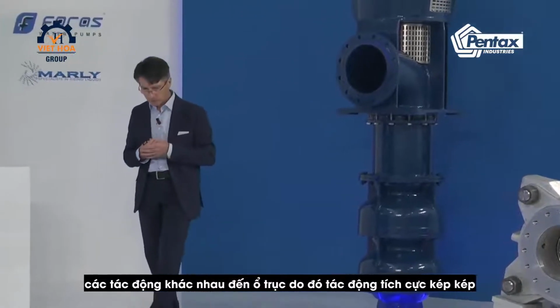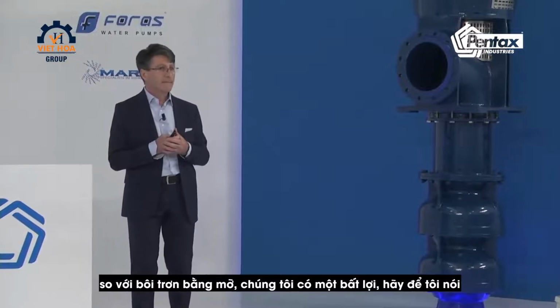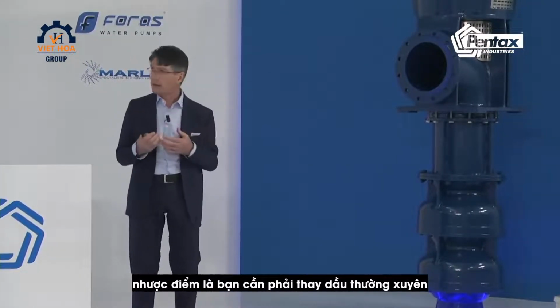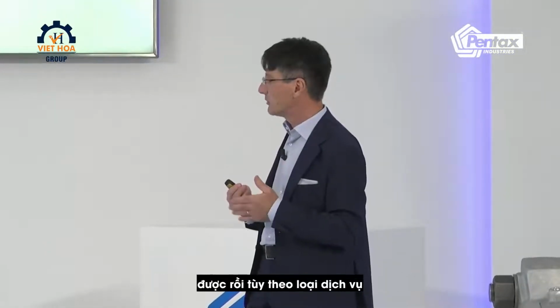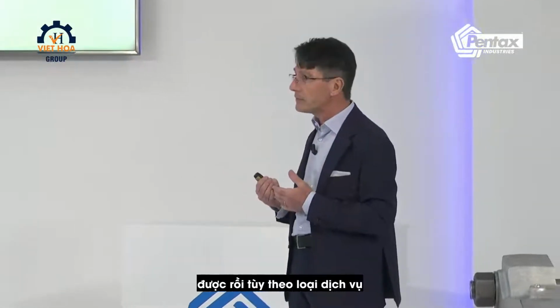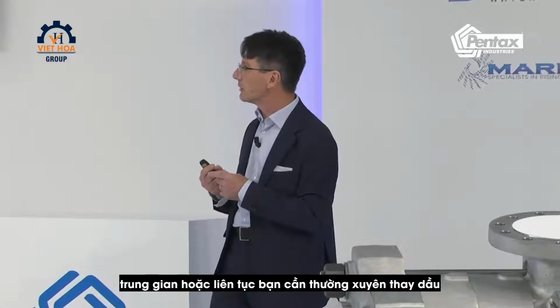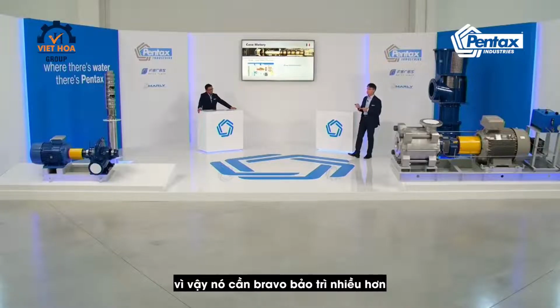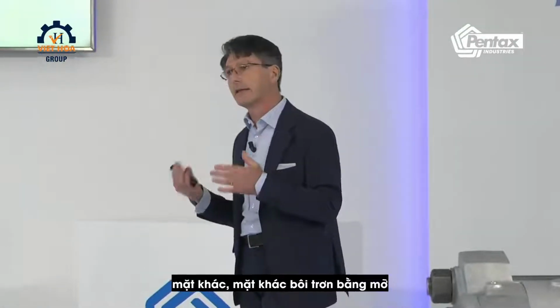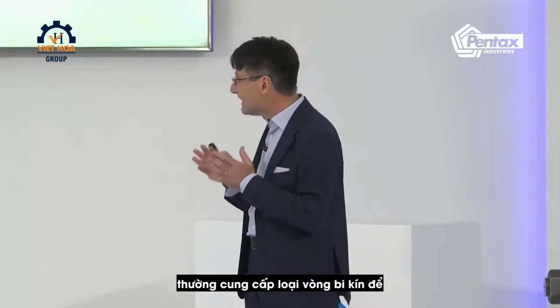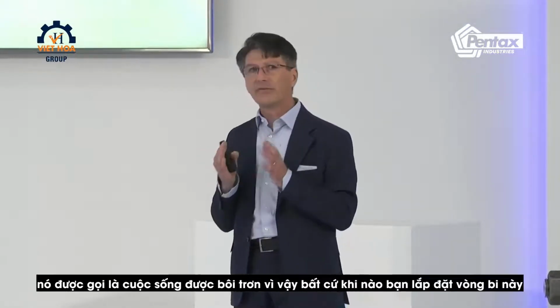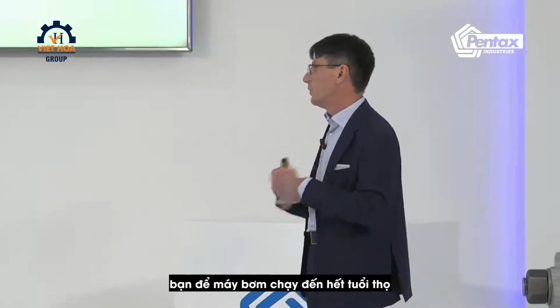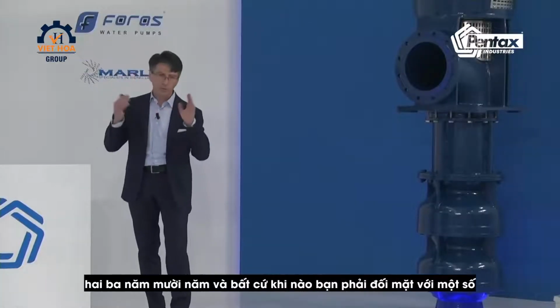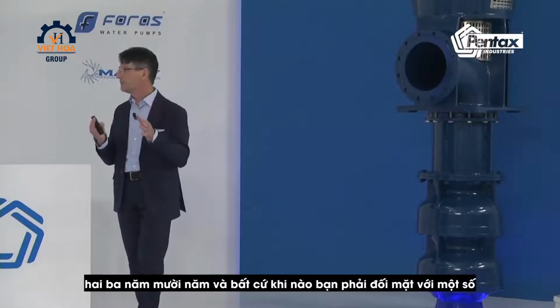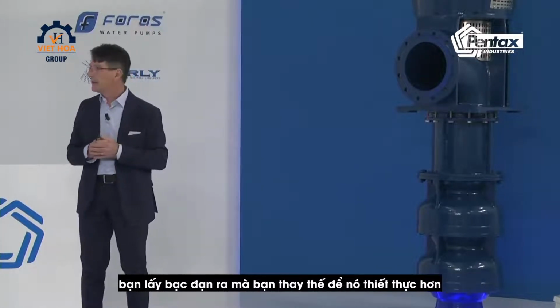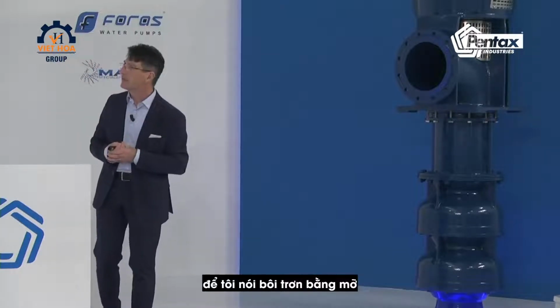So double positive effect. Compared to the grease lubrication, we had a disadvantage, let me say, that regularly you need to change the oil. So according to the type of service, intermediate or continuous, you need regularly to change the oil. So it needs more maintenance. On the other hand, grease lubrication normally is provided with a sealed type of bearing, so it's so-called life lubricated. Whenever you install this bearing, you let the pump running up to the end of the life, 2, 3 years, 10 years, and whenever you face some problem, you take the bearing out and you replace. So it's more practical, let me say, the grease lubrication.